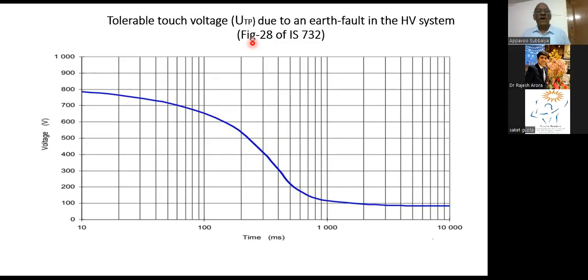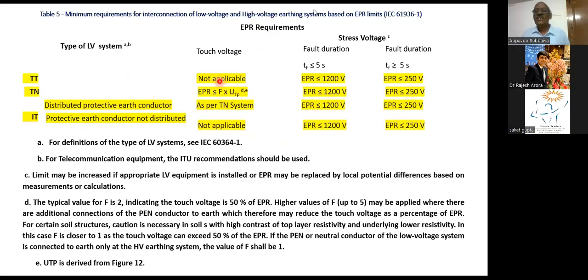And this is another table that has been brought. This is actually IS IEC 61936 part 1. It prescribes standards for designing earthing in installations exceeding 1 kV. This is up to 1 kV only, domestic premises. This is the important standard which is prescribed for designing earthing. This is on par with IEEE 80.